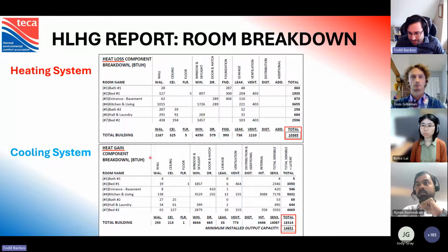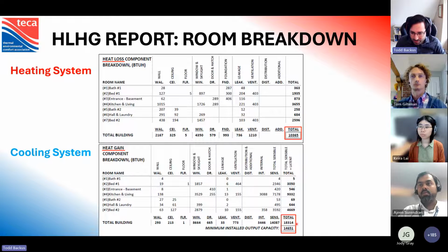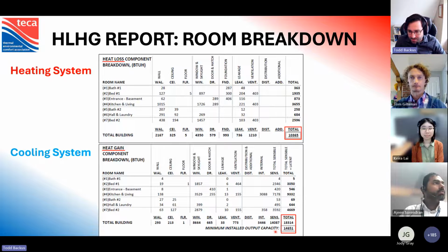The way the CSA F280 calculator works is it calculates the sensible cooling required, and then it times it by 1.3 to simulate the latent load. It's a shortcut, but it allows a very complicated calculation to be sidestepped. So here we have our total heat gain load. Now be aware that CSA allows the minimum capacity for cooling to be 80% of the total load. So that's what this box is.